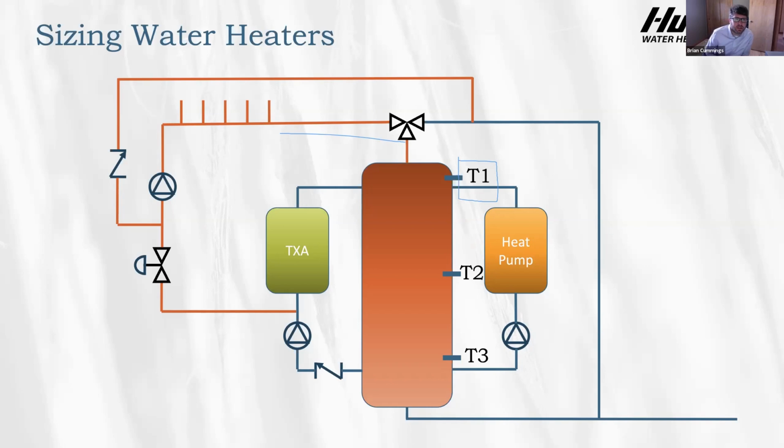Domestic water heat exchanger inside the heat pump. Yes. How is that mitigated? If it's an outside mounted heat pump, there's a pump and a heat exchanger in there, and all piping is heat traced. The other thing, of course, is that it could be mounted inside if you're concerned about that, and ducted outside, depending on where you have space in the building as well. But no, it's the heat trace that keeps it from freezing in most cases.